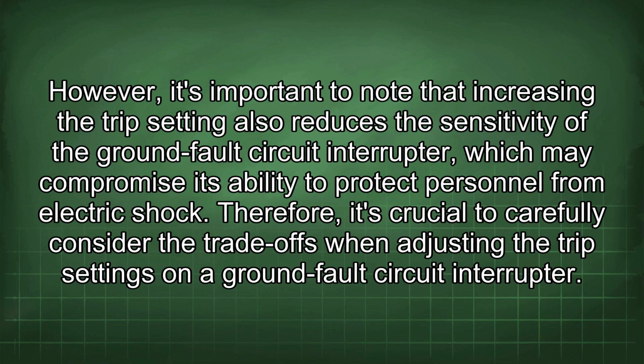However, it's important to note that increasing the trip setting also reduces the sensitivity of the ground fault circuit interrupter, which may compromise its ability to protect personnel from electric shock. Therefore, it's crucial to carefully consider the trade-offs when adjusting the trip settings on a ground fault circuit interrupter.